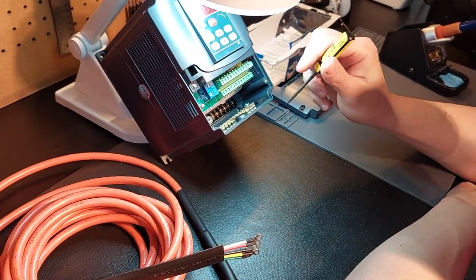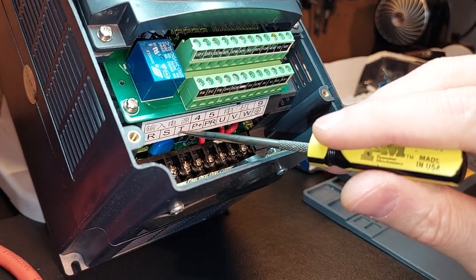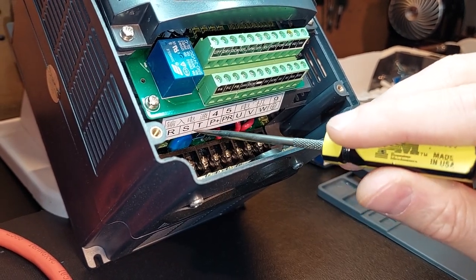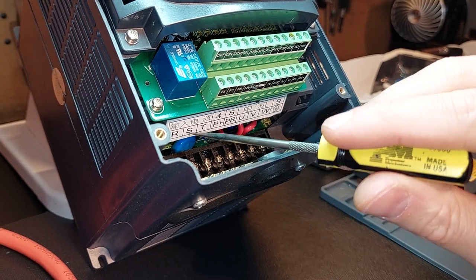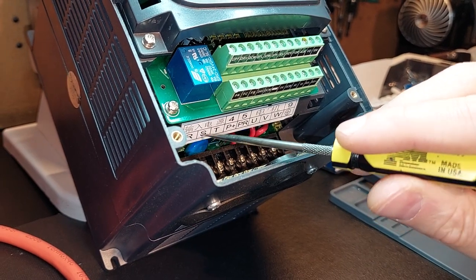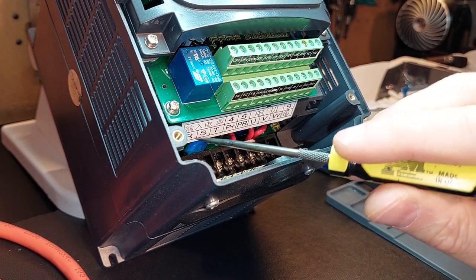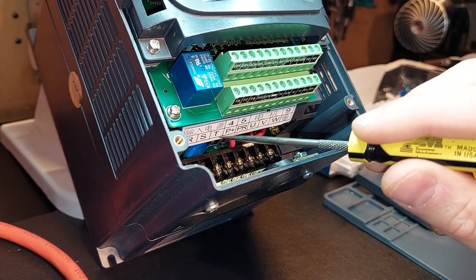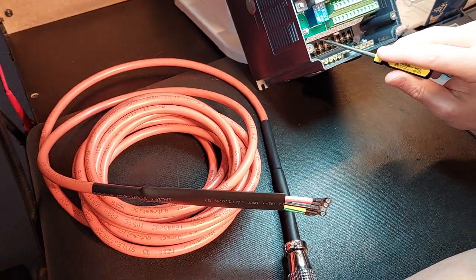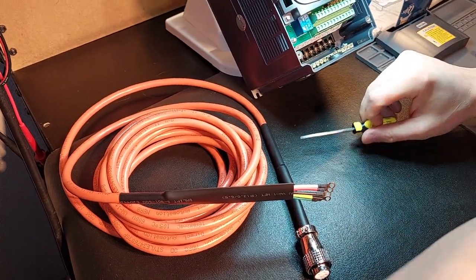Just to cover one other detail: your power cable coming in to power the VFD has R, S, and T. You can use any two of these to connect your power cable. If it's single-phase 220, you're going to use R and S, R and T, or S and T — it doesn't matter because it's single phase and 220 will have two legs of power. If you have three phase, just connect R, S, and T in any arbitrary configuration. It does not matter — you have three-phase power, and each power leg goes to an individual terminal.